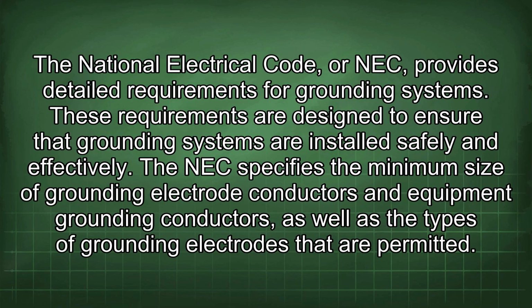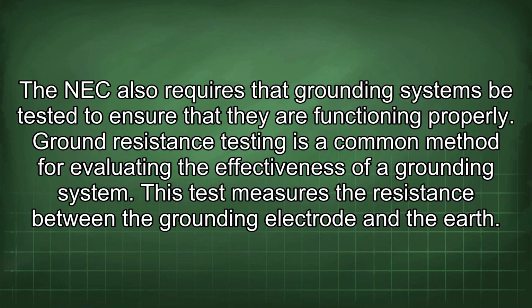The National Electrical Code, or NEC, provides detailed requirements for grounding systems. These requirements are designed to ensure that grounding systems are installed safely and effectively. The NEC specifies the minimum size of grounding electrode conductors and equipment grounding conductors, as well as the types of grounding electrodes that are permitted. The NEC also requires that grounding systems be tested to ensure that they are functioning properly.